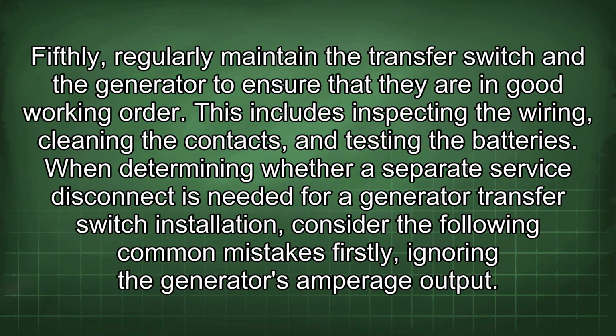Fifthly, regularly maintain the transfer switch and the generator to ensure that they are in good working order. This includes inspecting the wiring, cleaning the contacts, and testing the batteries. When determining whether a separate service disconnect is needed for generator transfer switch installation, consider the following common mistakes.